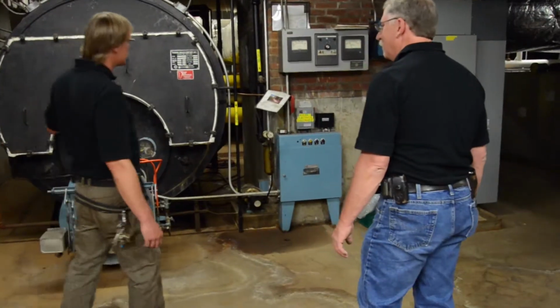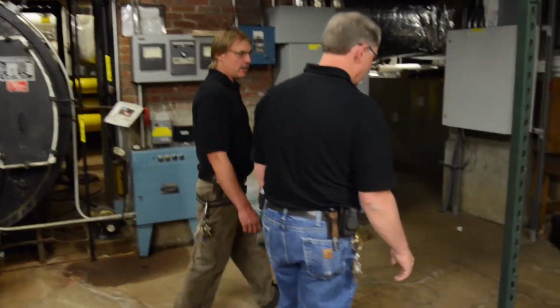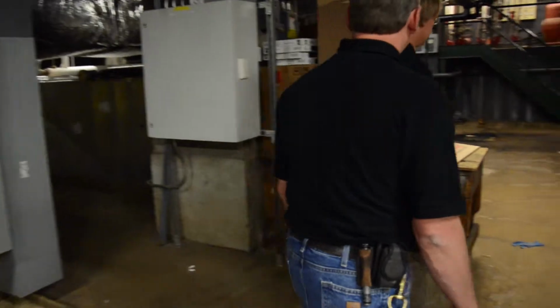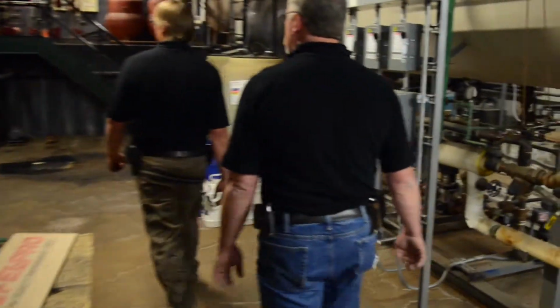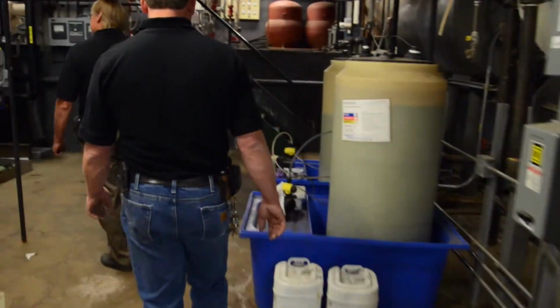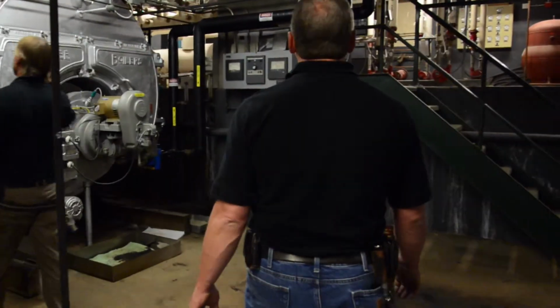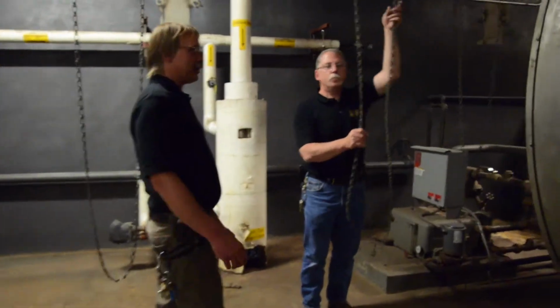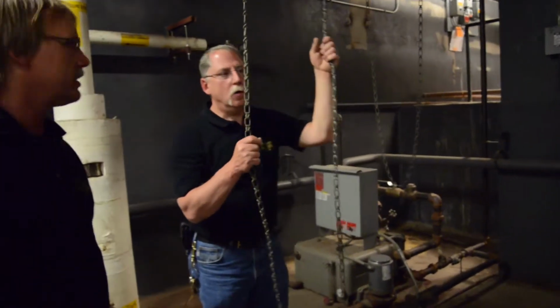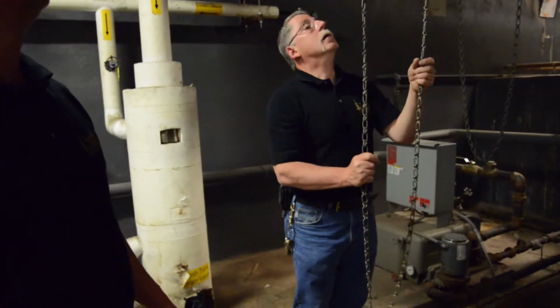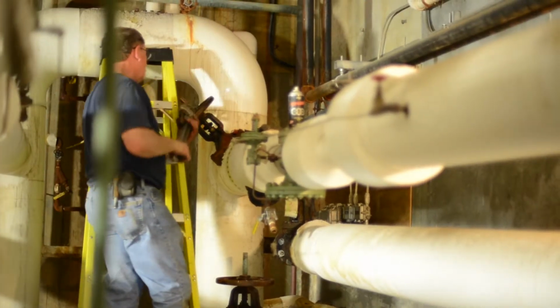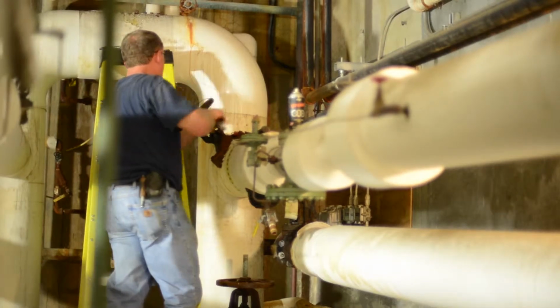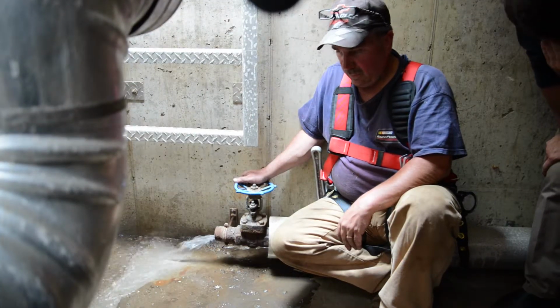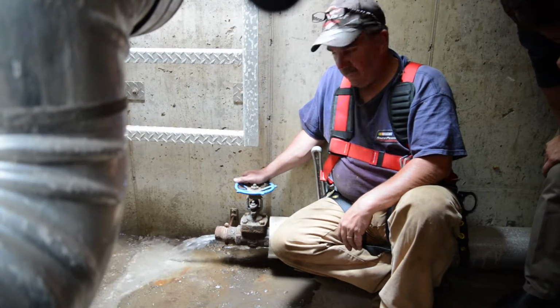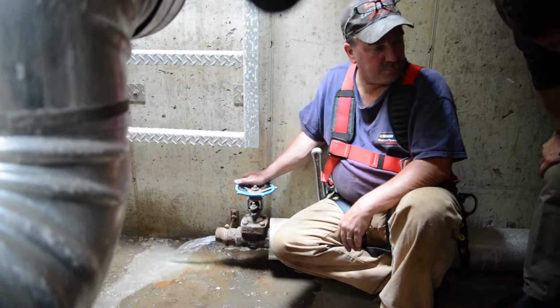In supplement to the central heating and cooling system at the central plant, there are several additional boilers located in major buildings across campus that provide backup heating and cooling for the campus when the central plant cannot. Before the central plant can be shut down, these boilers must be fired up. Once the satellite boilers are online, the entire central plant is ready to be shut off so that the lines can cool in time for maintenance. At 6 p.m. on the Sunday of graduation, the main boilers are shut off, the steam lines drained, and everything is powered down.